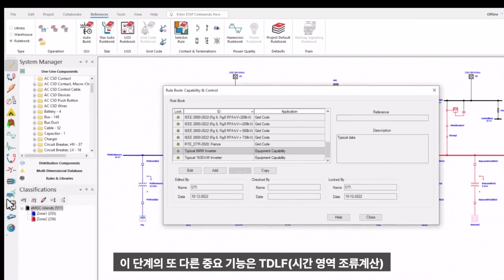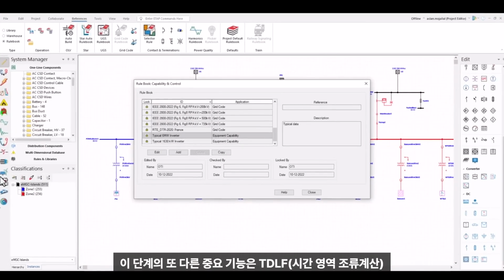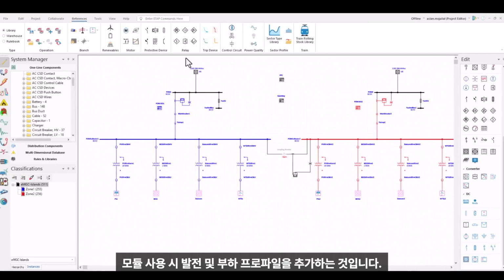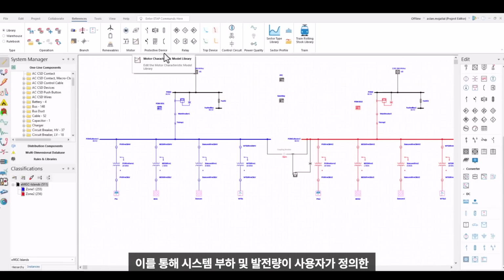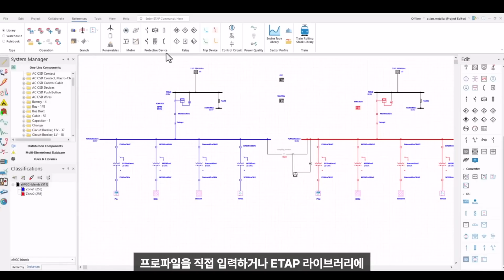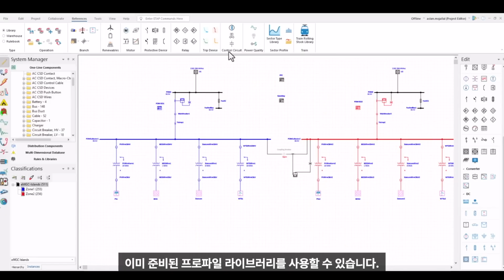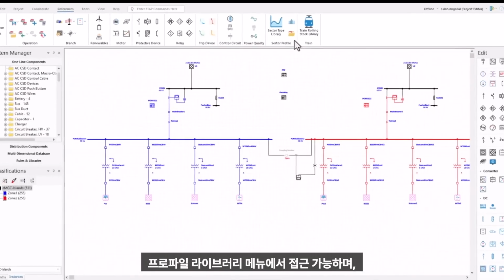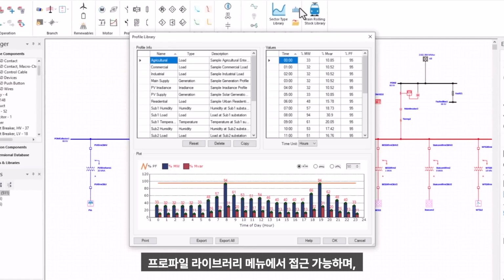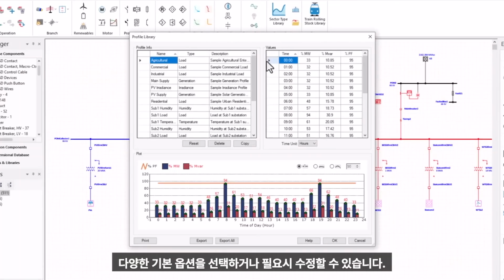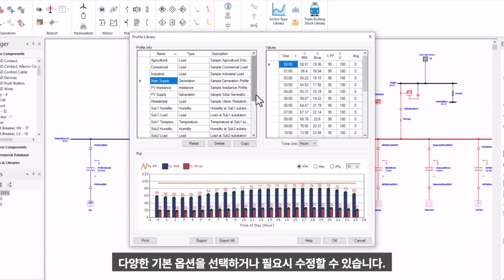Another important feature at this stage is the ability to add generation and load profiles when using the time domain load flow module, or TDLF module. This allows the system load and generation to follow a time-based profile that you define. You can either enter your own profiles or use the profile libraries already available in ETAP. These profiles can be accessed through the library and then the profile library, where you can select from a wide range of predefined options or modify them as needed.